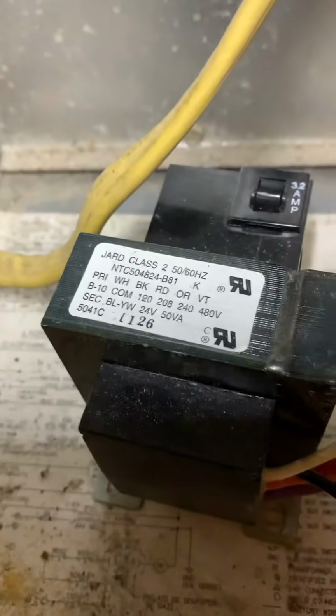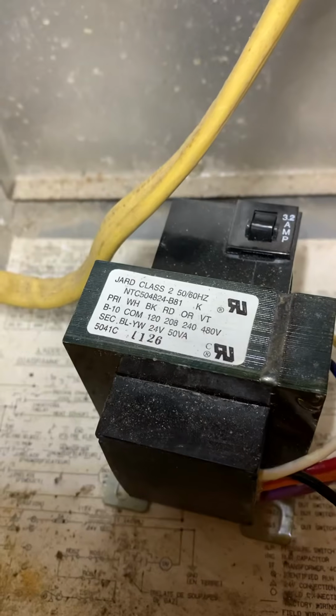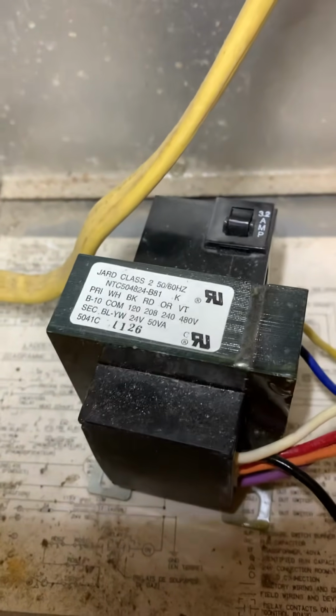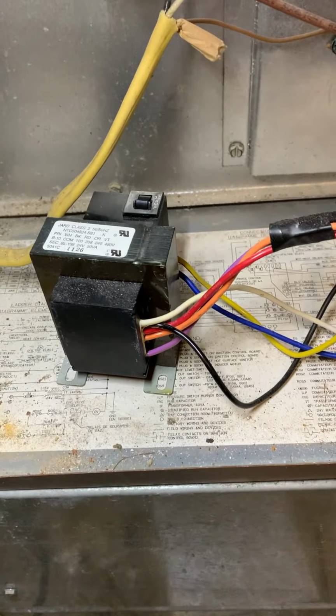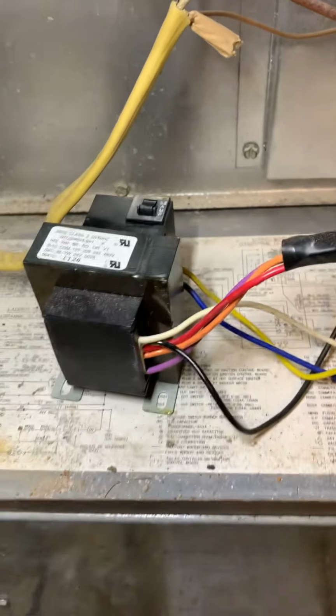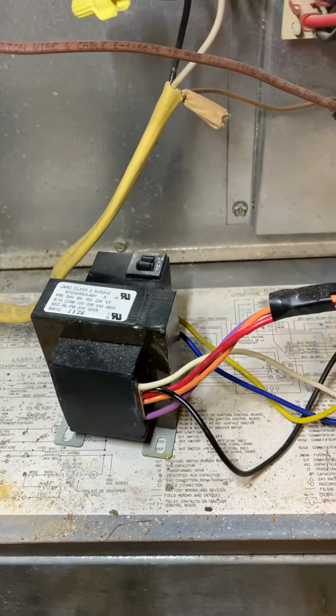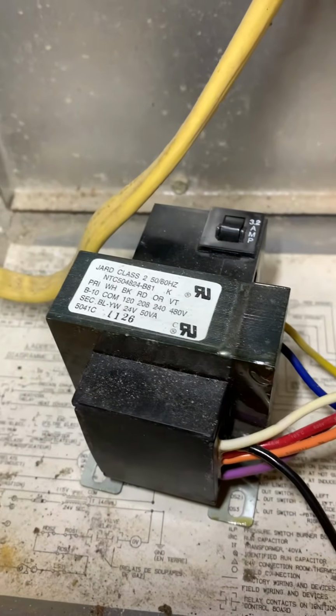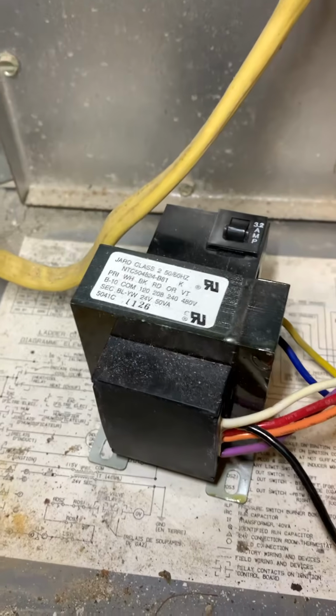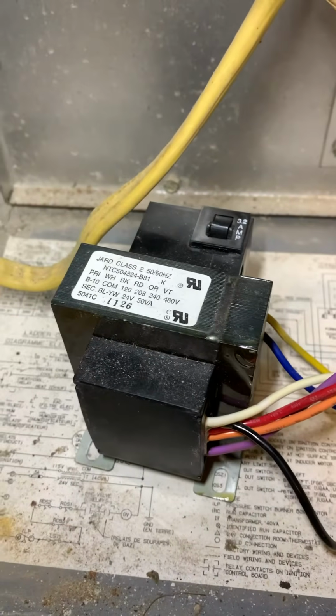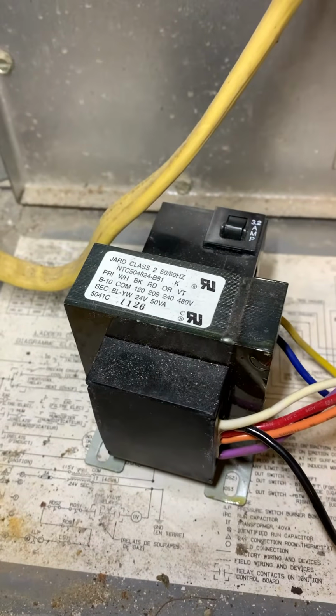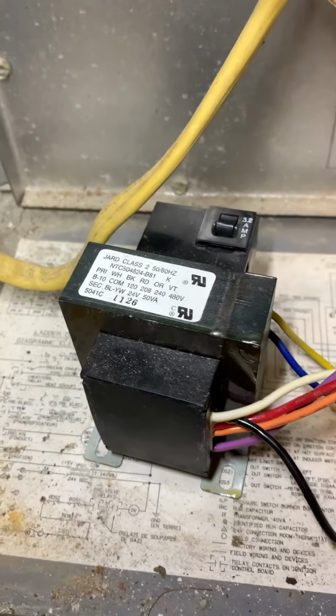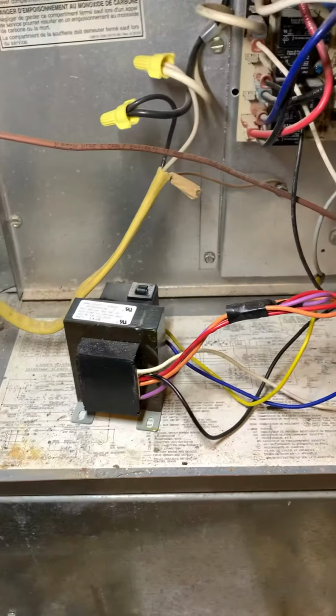And like I said, you have 50 VA. See in the bottom right hand corner, 50 VA, 24 volts. So you divide the 24 into that 50, which you shouldn't have more than, say, 2 amps going through this. That's why it's going to pop right at 3.2. All right, and it protects the board and it protects the transformer. So if you ever want to know how much amps can go through a transformer, just take the secondary, the low voltage, by the VA. So if it was 40, it would be less than 2 amps. If it's 60, it's going to be almost 3 amps, that should be the maximum before it's going to pop, okay? On this one here, it's 24 volts. Divide that by the 50 VA and it gives you around 2 amps, which this was 0.60 while everything was running, even the heat. Okay, so that was the issue.